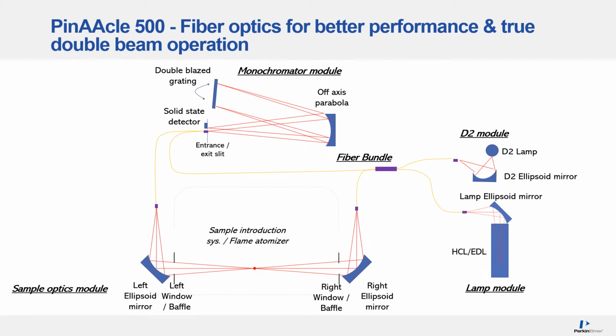To give you a better idea of how the fiber optic bundles are used within the system, this diagram should help demonstrate that. The optical system design utilizes fiber optic cables throughout the system, as you can see. The PinAAcle AAs have a real-time double beam system along with the solid state detector with dedicated areas for sample and reference beams. The use of a new optical design and the solid state detector allows the simultaneous measurement of the sample and reference beams for true double beam operation in flame mode.